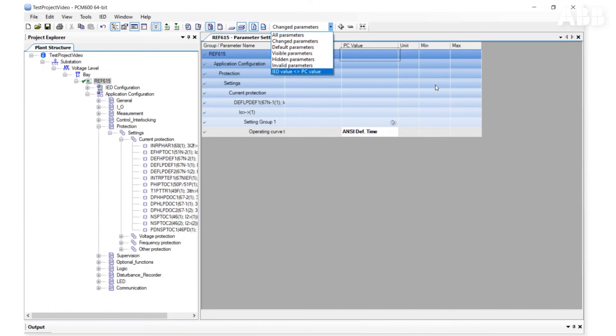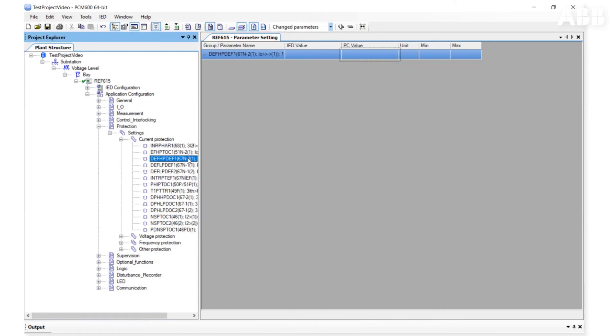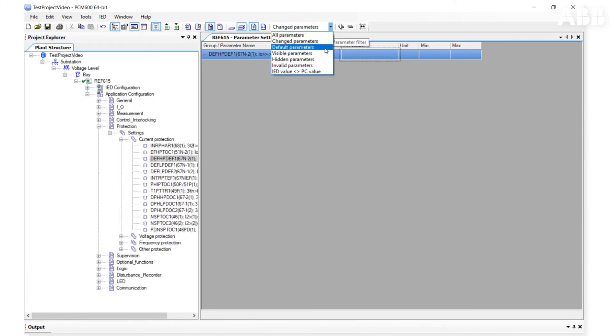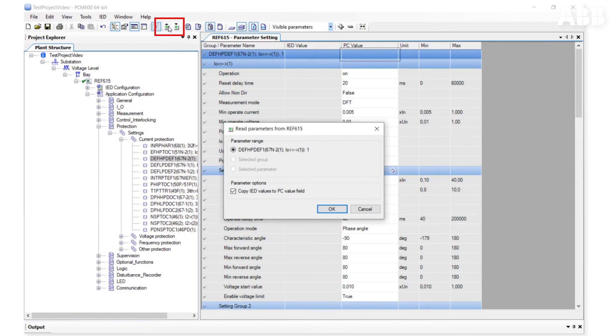To read parameters, we need to select the item in the plant structure for which we want to have parameters read and then click on the button Read Parameters from IED. Let's try to do that if only one function is selected and there are no parameters selected in the main view. In this case, PCM600 will read all the parameters belonging to the selected function.